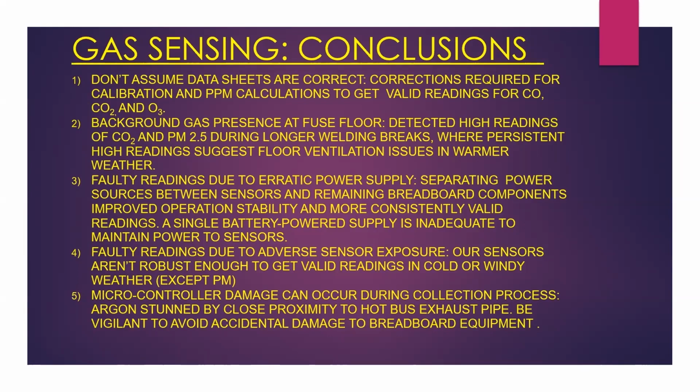So while we were conducting our sessions, we detected high readings of carbon dioxide and PM 2.5 during the longer welding session breaks, where these persistent high readings did suggest that there could be floor ventilation issues in warmer weather.